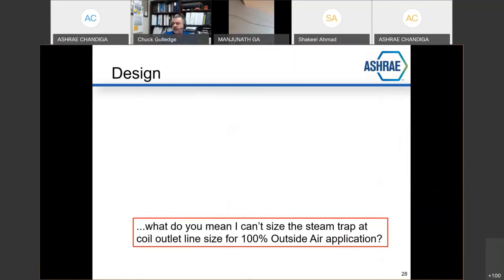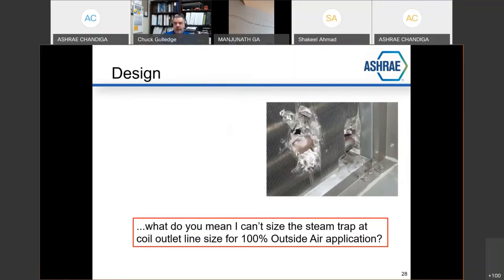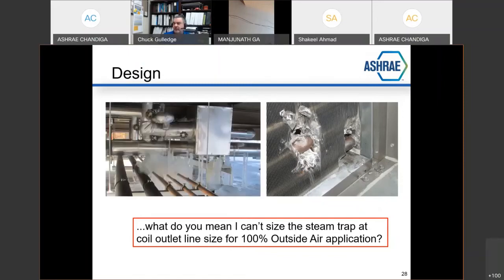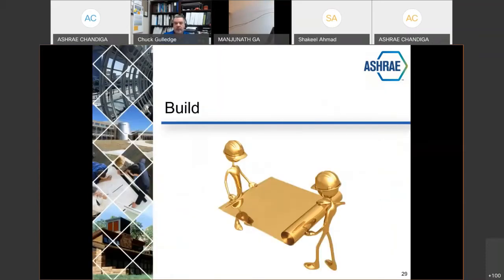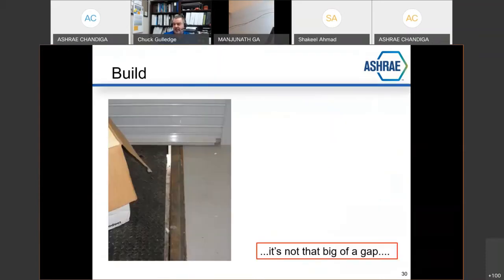What do you mean I can't size the steam trap at coil outlet line size for 100% outside air application? Well, if you don't pay attention to what you're doing and size the trap for the load and the safety factor, you get something called a busted coil. And all of this happens because the trap, a puny little trap, can't move the condensate fast enough. And look what happens. You get ice and you get a busted coil. So simple to avoid if we size steam traps appropriately for the load with the proper differential pressure, with the proper safety factor. So let's get into the construction side of this.